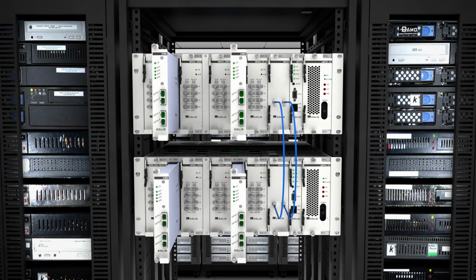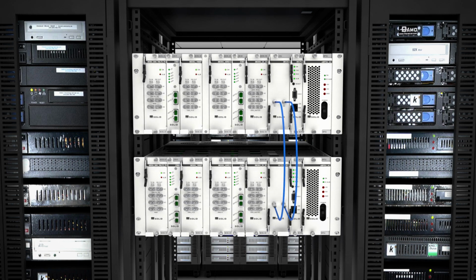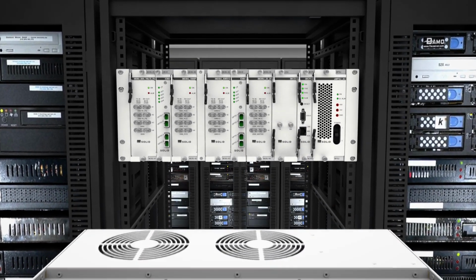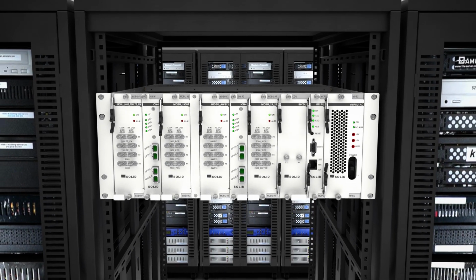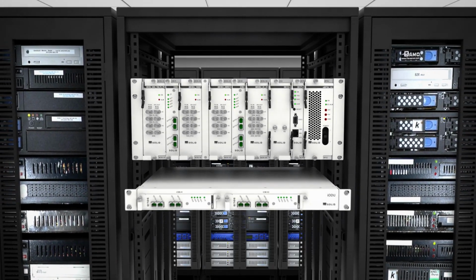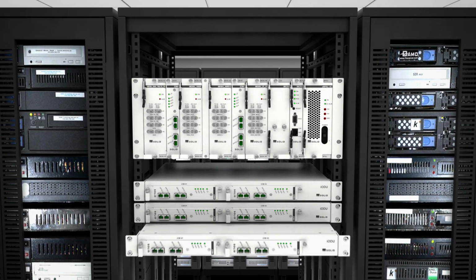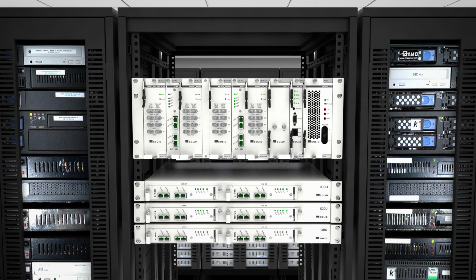Up to 2 optical modules fit in the iBIU. Each card supports either 1 or 4 optical connections to DAS remotes. For large systems, expanded optical port capacity is available. Up to 3 IODUs may connect to the main iBIU, providing up to an additional 24 optical ports.